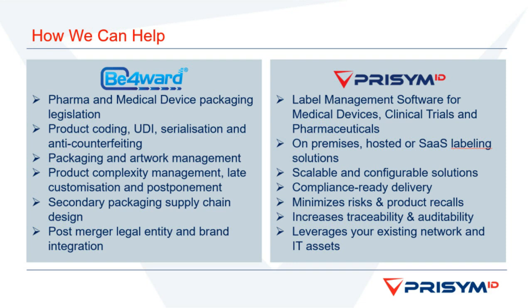But principally, the requirements for what makes up the UDI in terms of the DI and the PI for your FDA and your EU MDR are very consistent, and you should be able to use the same solution to meet those requirements. If anything, the EU MDR is putting additional restrictions and requirements on top of what the FDA introduced initially.